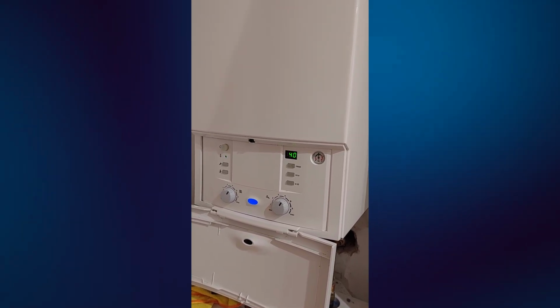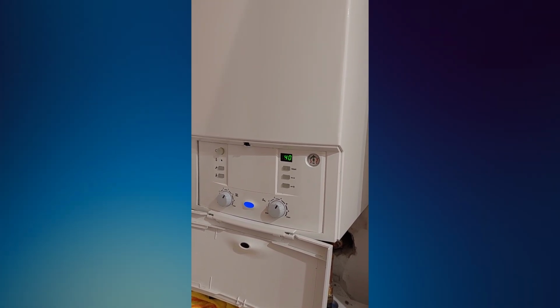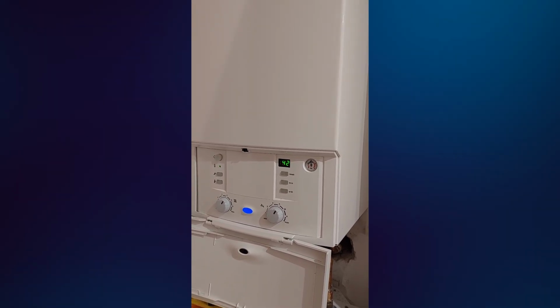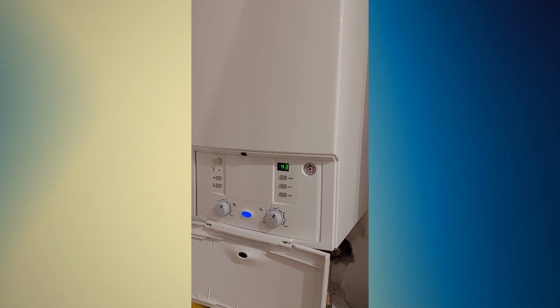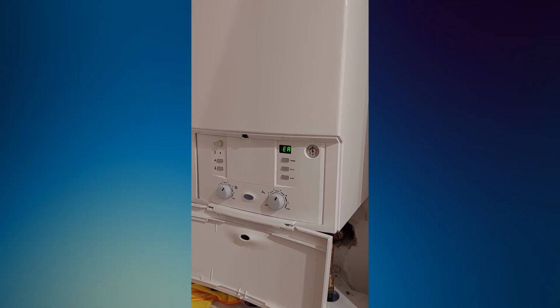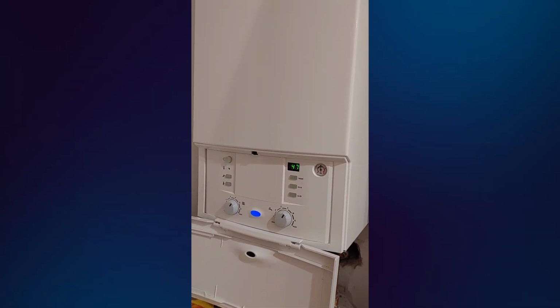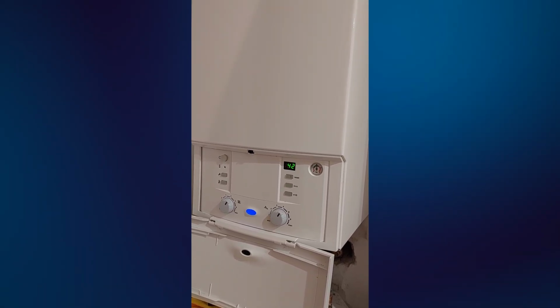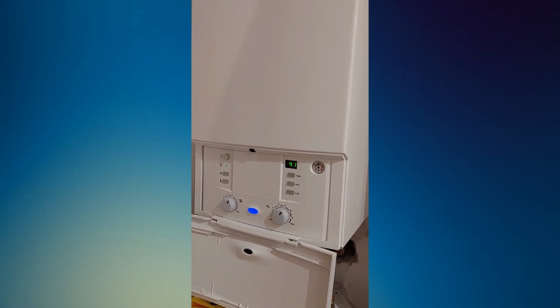The boiler may try to ignite several times, then lock out for safety. You may hear the fan start, you may hear clicking from the ignition, and the burner may light briefly, but if the control board does not see a proper flame signal, the boiler will stop and show the EA code. This is not just an inconvenience, it is a gas appliance safety lockout.